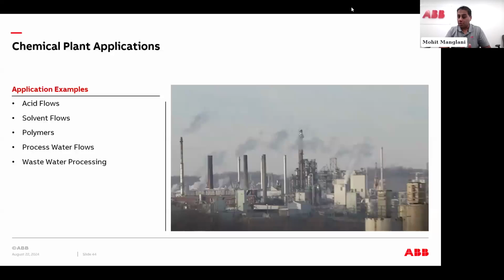If you're doing chemical injection into a process line and a mag meter's there, you want to make sure that injection is downstream of the meter, not upstream of the meter. I wanted to add that because I saw the acid flow here. It just came to mind. Acid flows, sodium hypo, sodium hypochlorite, chlorine, bleach, you name it. Solvent flows, polymers. Big thing with polymers is you want to make sure that they have conductivity.